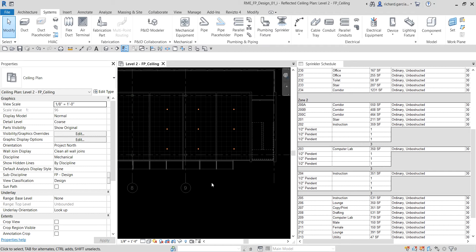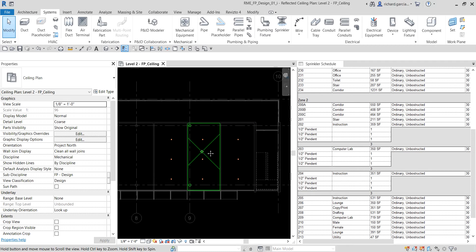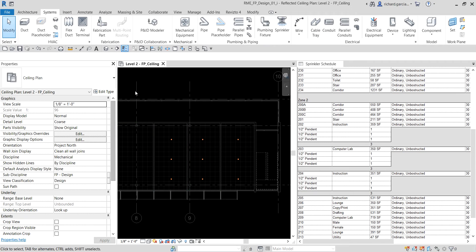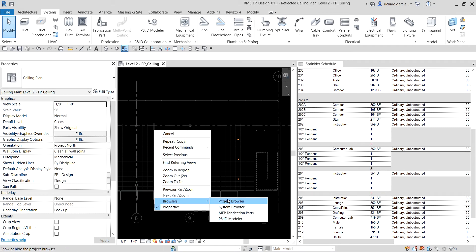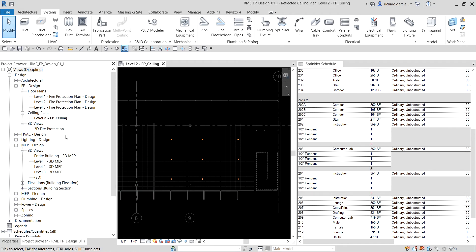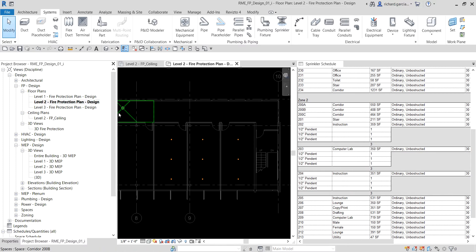For the non-hosted sprinkler portion, we'll specify the vertical offset or elevation of the sprinkler and then use the Array tool to copy them. I'm going to open the floor plan view instead of the ceiling plan — right-click in the Project Browser, find the floor plan design, Level 2 Fire Protection Plan Design, and double-click it.